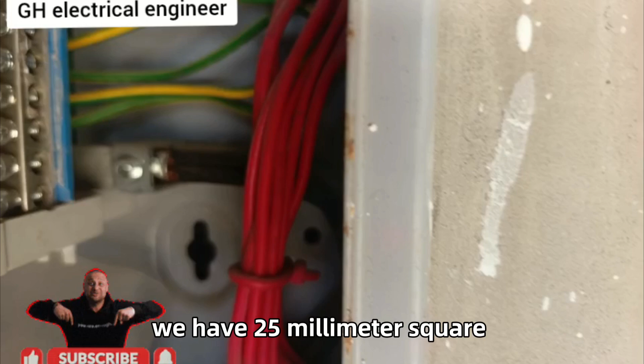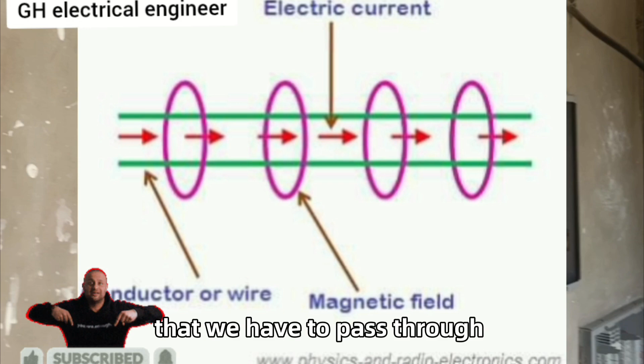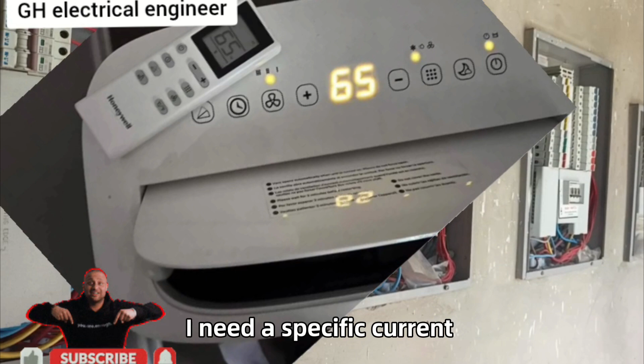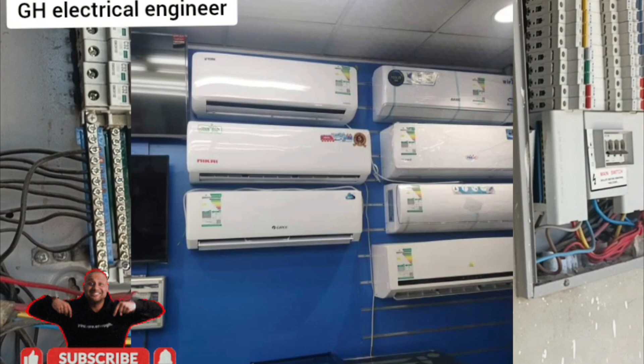Based on that, we design all these breakers around the certain current that has to pass through. For instance, an air conditioner needs a specific current to pass through for it to work properly. Common lighting needs a specific current to work perfectly and last timelessly. If you put it on another current, trust me, it will only last 3 months, 6 months, or a year - it won't last timelessly. All of this is achievable only if you do a specific design for your client. What kind of design?